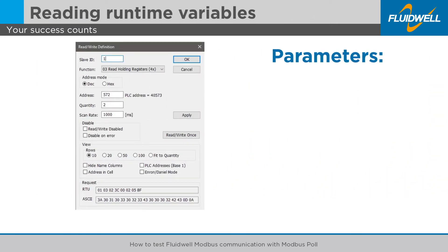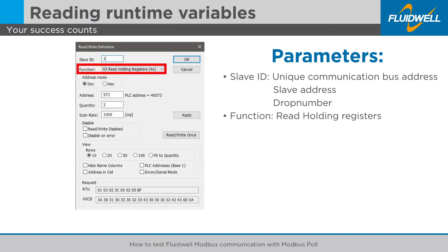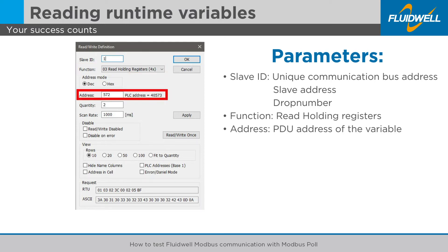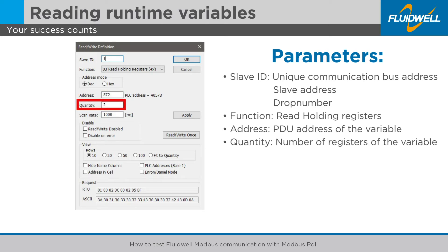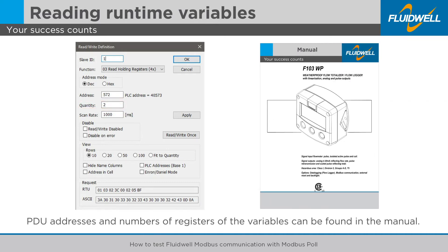For reading runtime variables, you will need to set the following parameters. Slave ID – this is the unique communication bus or slave address or drop number. Function – for reading from Fluidwell devices, select 03 read holding registers. Address – this is the PDU address of the variable. Quantity – this indicates the number of registers of the variable. PDU addresses and numbers of registers can be found in the manual of the Fluidwell device.